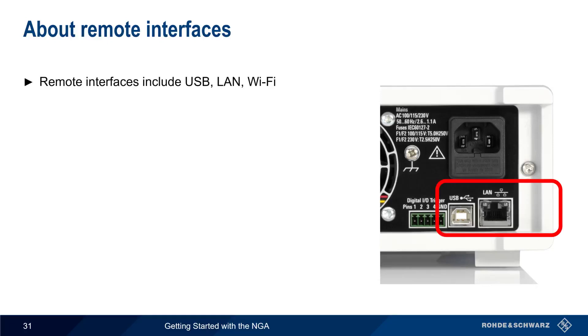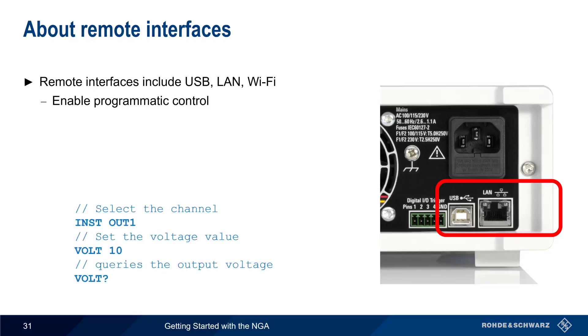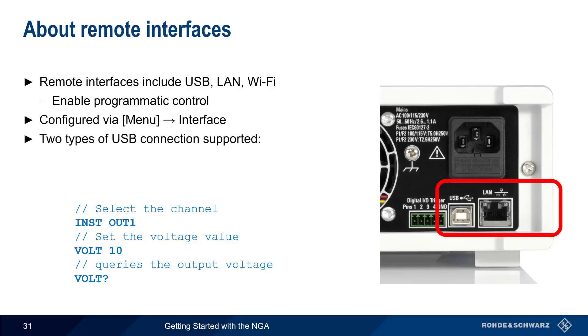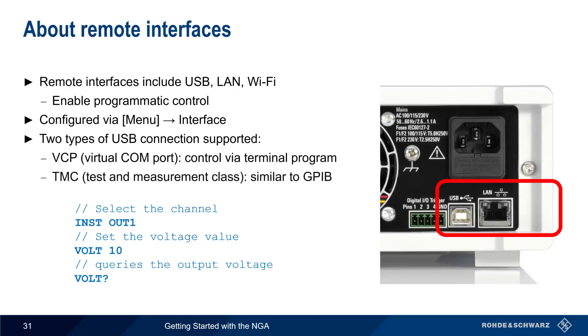Digital triggers can be used to remotely control or monitor basic NGA functionality, but more sophisticated remote control is also possible over the NGA's remote USB, LAN, and Wi-Fi interfaces. These remote interfaces enable programmatic control — that is, they allow you to both configure and read values from the NGA using standardized commands. Remote interfaces are configured via menu interface. Note that two methods of USB connection are supported: the first is the virtual COM port, which enables control over a simple terminal interface; the second is the test and measurement class, which provides functionality similar to the older GPIB methods of remote control. Please see the NGA documentation for more information and a complete set of supported commands.